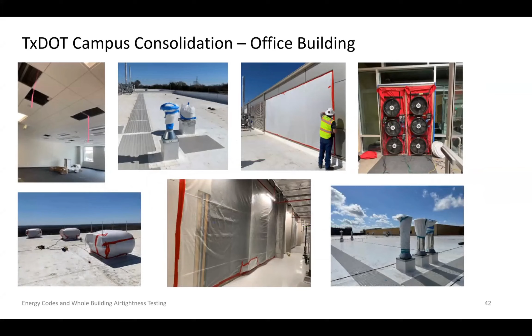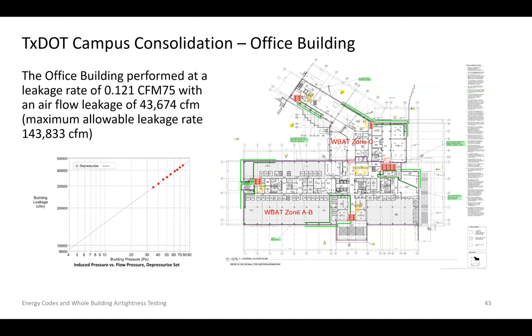So this is the first large building that this GC had done. That leakage rate was 43,000 CFM. What that means, from a maximum allowable of 144,000, is that for every minute that building was operating, there was 100,000 cubic feet per minute of conditioned air not being pushed through the envelope. So you don't even have to have complex energy modeling to know that there's tremendous savings available from that.